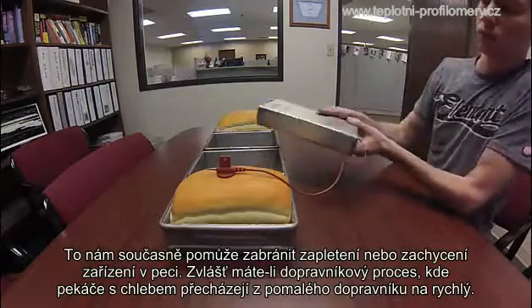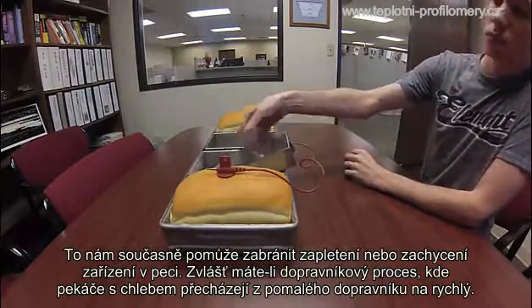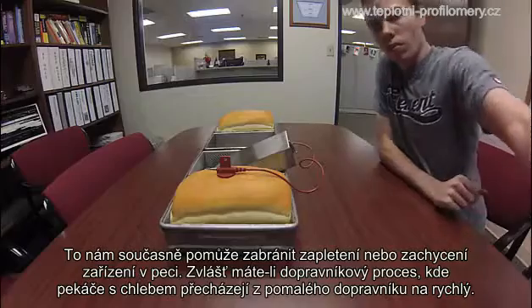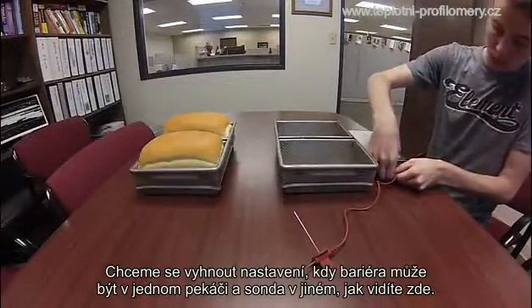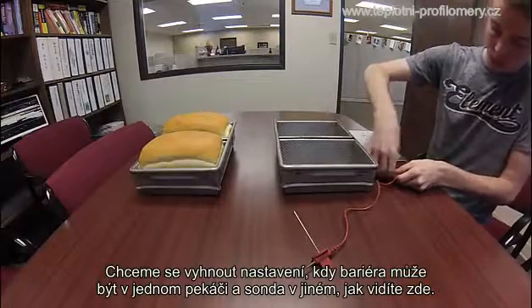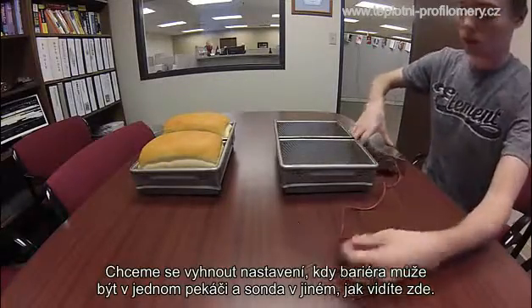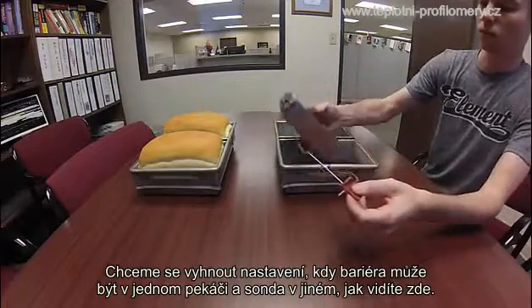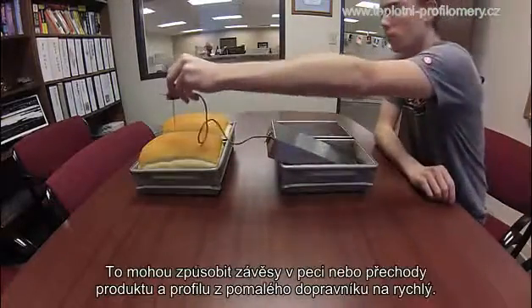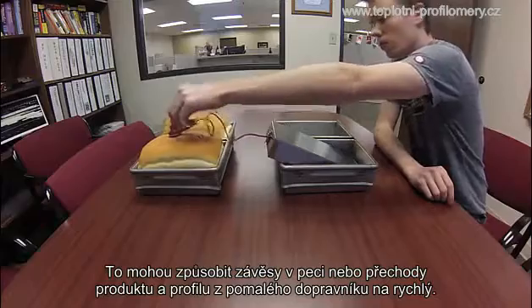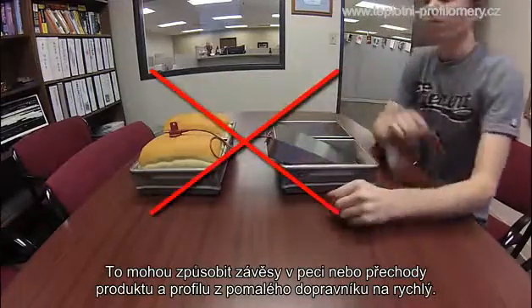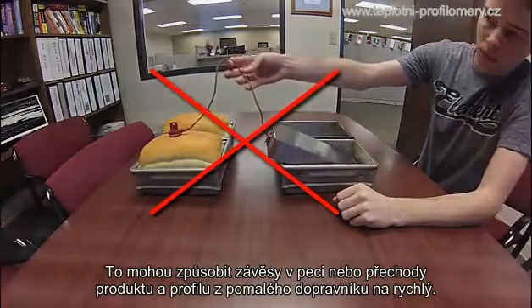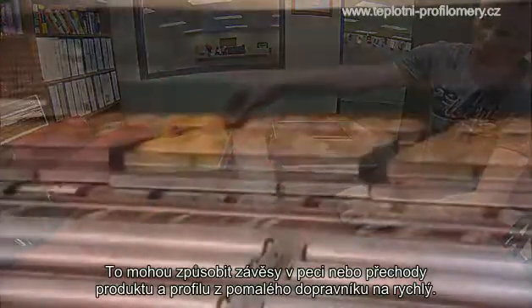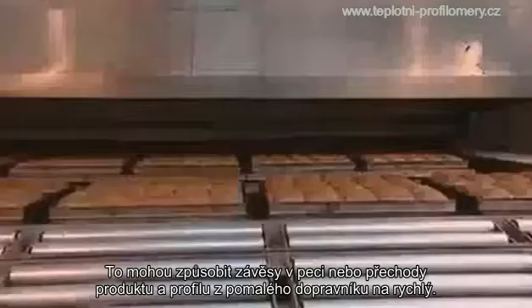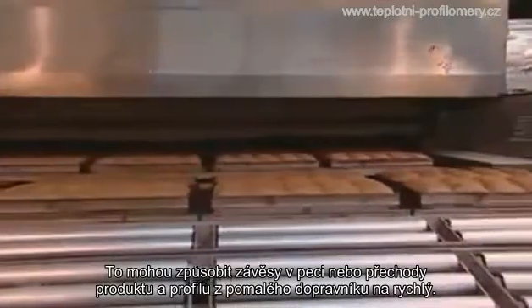This helps avoid the equipment from getting tangled or caught in the oven, especially if you have a conveyorized process where the bread pans switch from a slow conveyor to a fast conveyor. We want to avoid a setup where you may have the barrier in one bread pan and the probe in another, as that can cause hang-ups in the oven or along the process where the product and the profiler are changing from a slow conveyor to a fast conveyor.